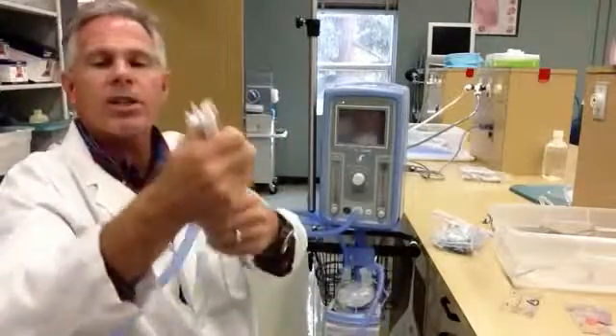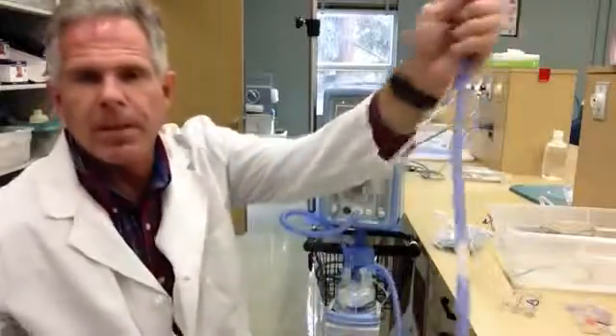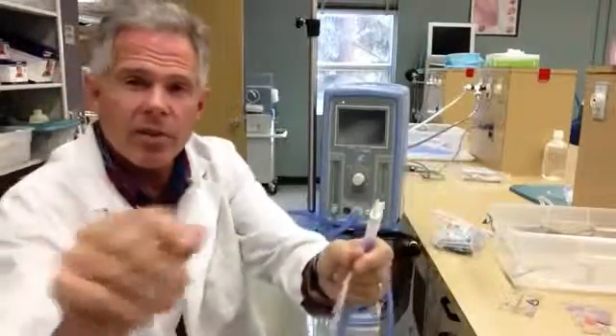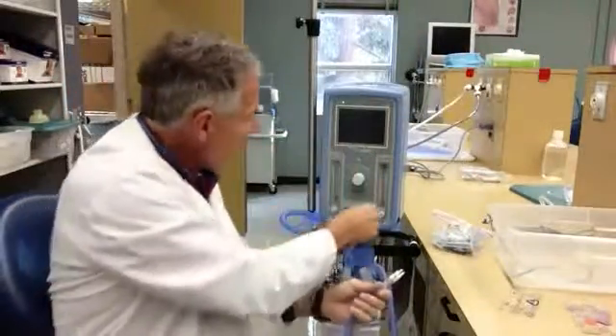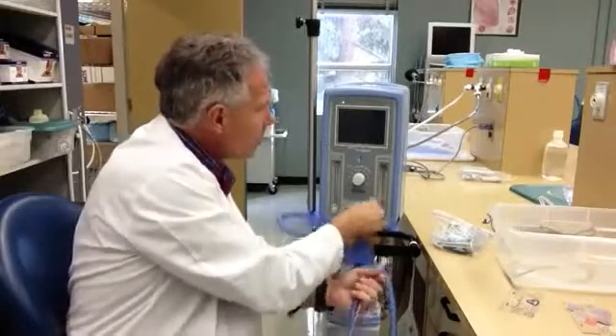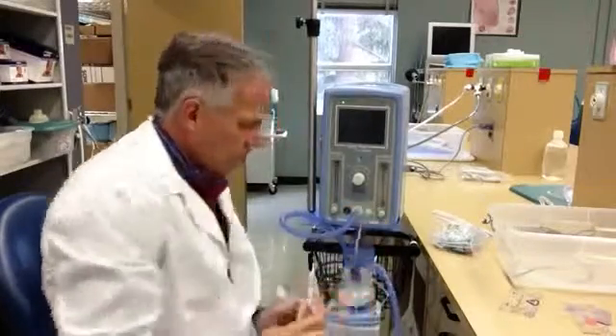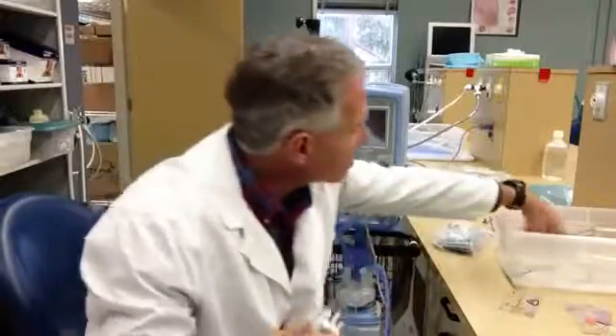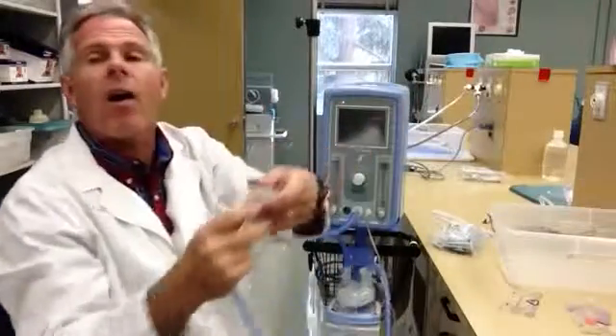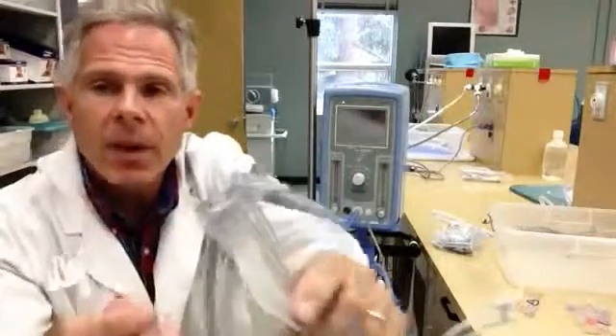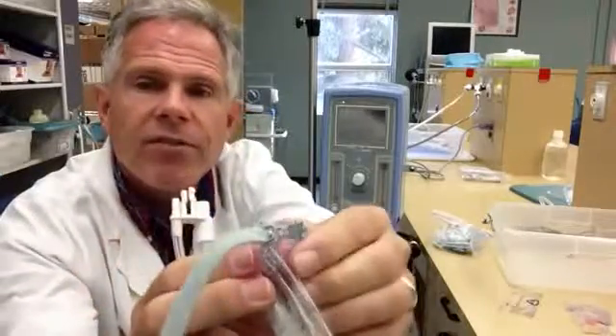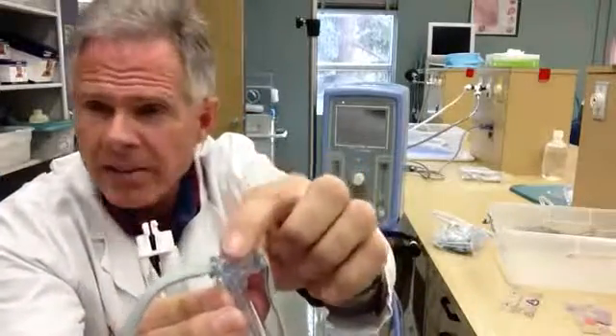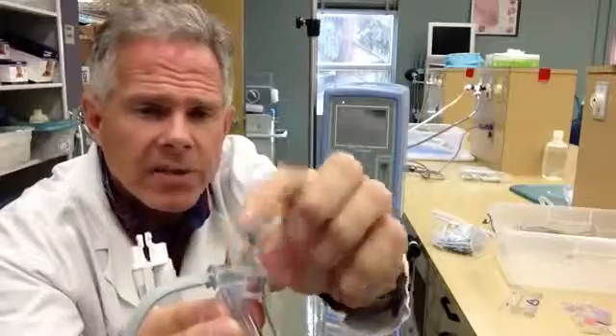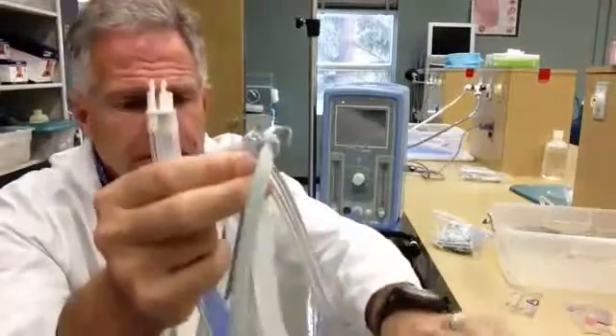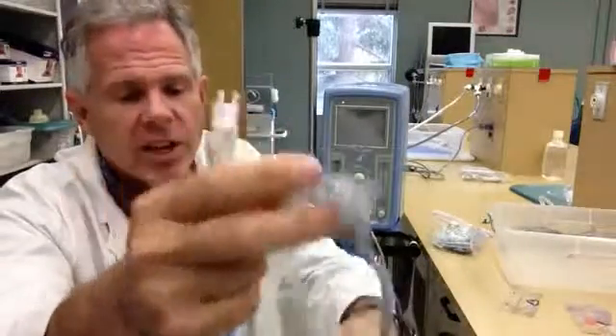And I've got my pressure monitoring line. It's also going to hook up directly to the ventilator. So we're going to take our pressure monitor line and hook it up to my proximal pressure right here. Okay. Now I've got the special patient circuit, and this is really the heart of the SiPAP device right here. You can fit a specialized nasal mask or these little nasal prongs, and I'll show you some of those in a minute. All right. And that's our patient interface.